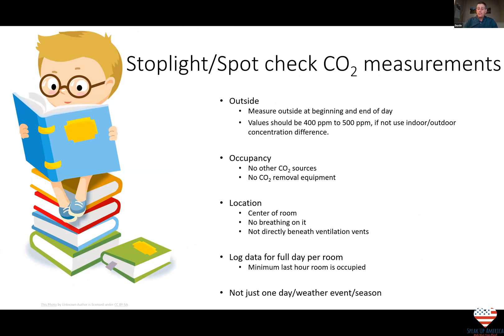To use CO2 sensors to check ventilation, place the sensor outside for five minutes. Make sure the room to be measured is occupied with normal occupants and use patterns, but has no non-human CO2 sources. Locate the sensor in the middle of the room and log the data for a full day. Ventilation changes depending on window operation, season, weather, and HVAC operation, so repeat this measurement on a regular schedule.